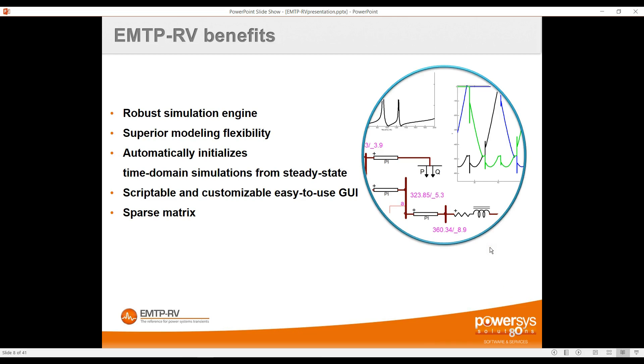A final major advantage is the sparse matrix technique used to solve the equations, which is critical for large grids. Without sparse matrix, computational time increases as the cube of the number of nodes; with sparse matrix, it increases proportionally. This makes it very easy to handle large networks, and some EMTP users model their full network — up to 100,000 buses — with no actual limit on network size.